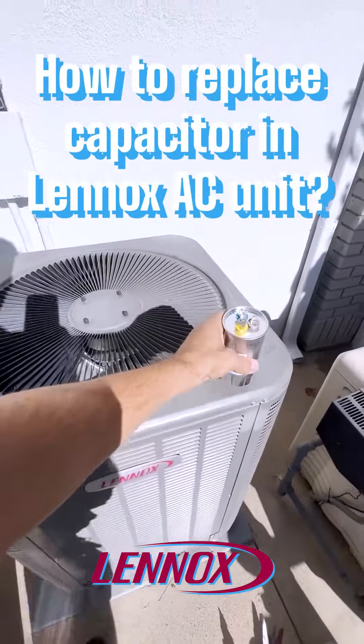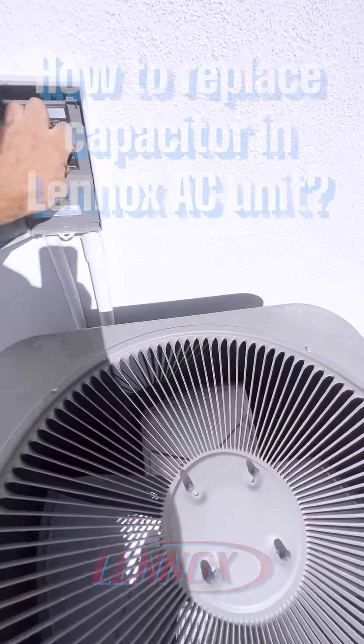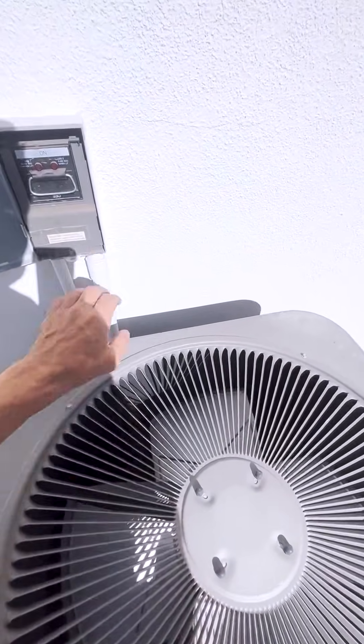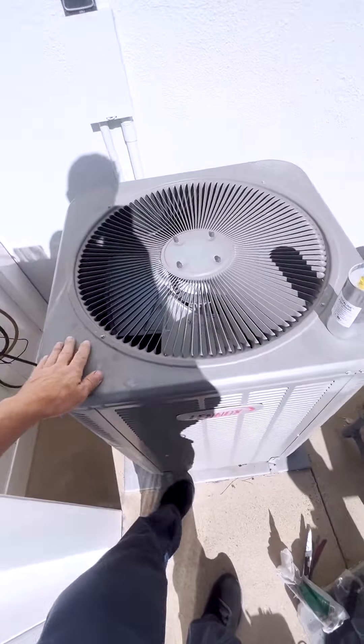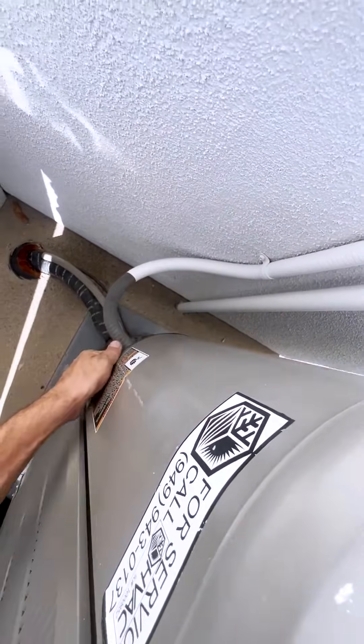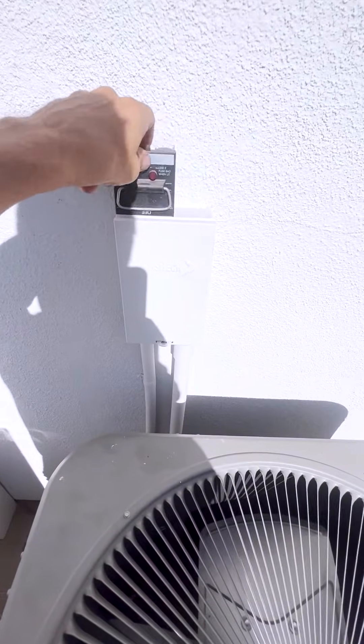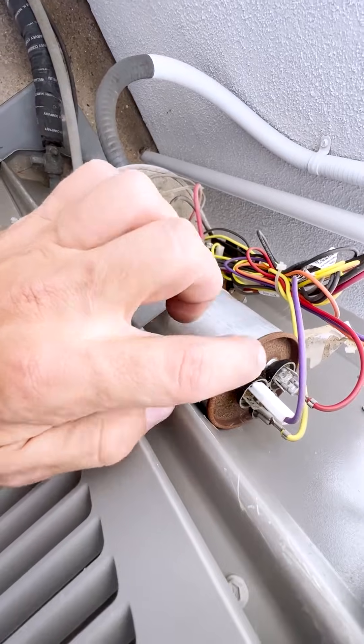We have this Lennox unit. When you turn on this unit, it just hums and doesn't start — it hums once in a while trying to start. Most likely the problem is the capacitor. We need to open the lid by taking these two screws out to find our capacitor. Don't forget to turn off power to your AC unit. This is a capacitor — you can usually tell it's bad by looking at it; sometimes they get swollen.